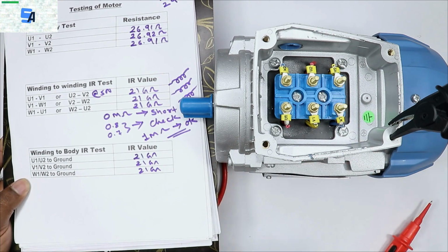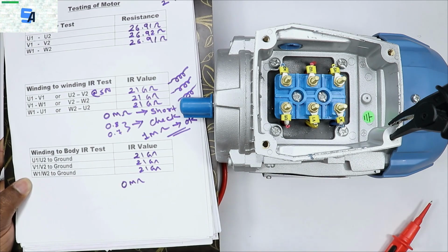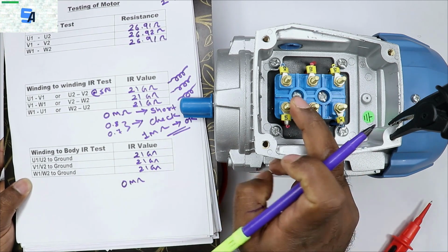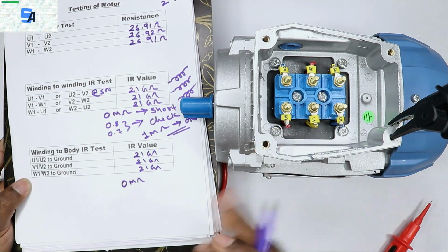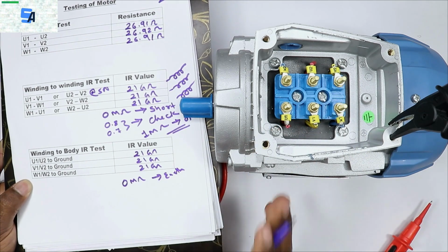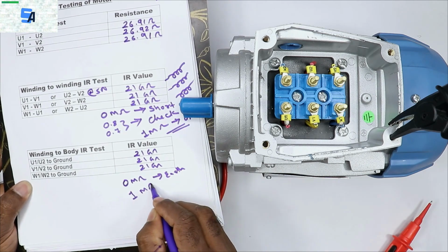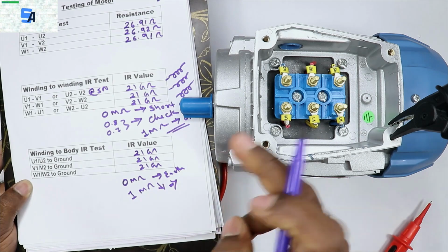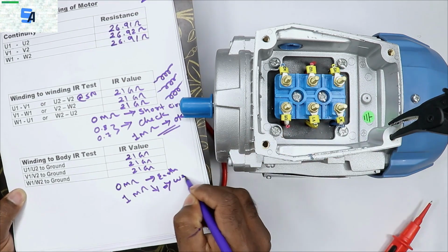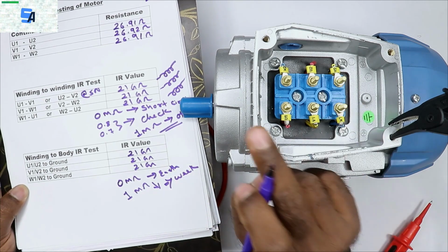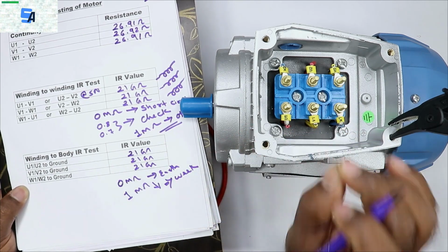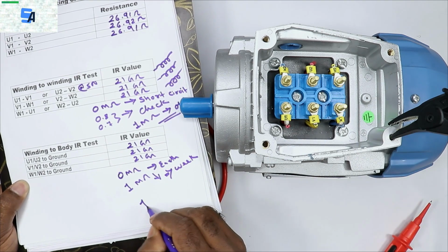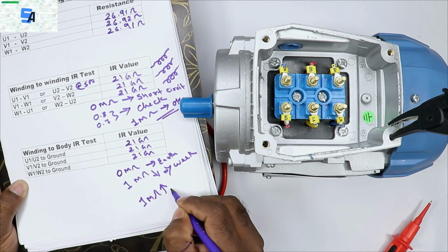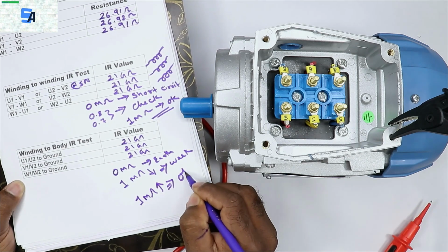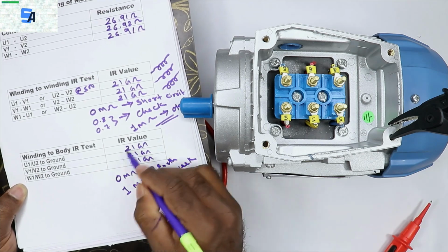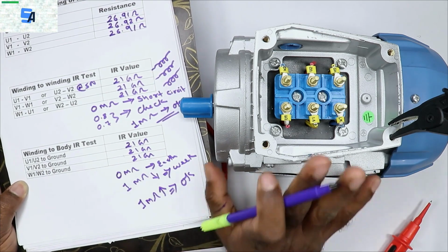Friends, in the testing we just did, if we got 0 mega ohm IR value, we would say the winding of the motor is connected with the body of the motor. It means an earth fault occurred. Besides, if we get less than 1 mega ohm IR value, we would say the insulation of the winding got weak. It means we have to apply insulation on the windings again or rewind them. Besides, if we get an IR value of more than 1 mega ohm, we will say the motor is alright. Right now we are getting 21 giga ohm IR value. This means the motor is alright.